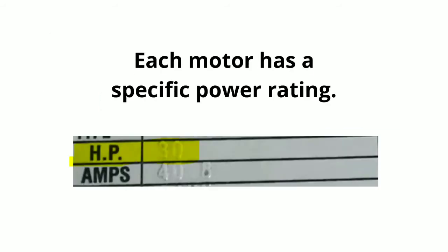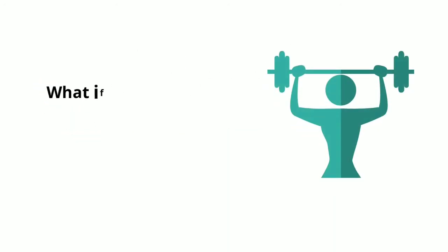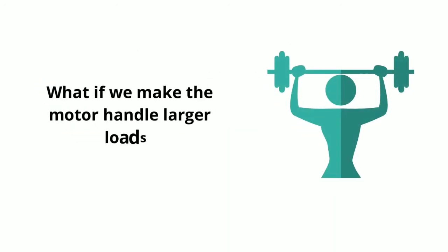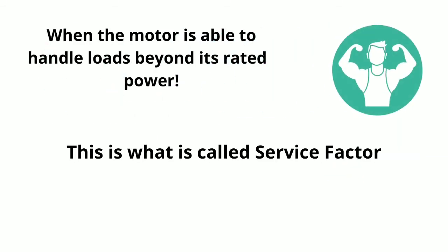Each motor has its power rating. This motor is 30 horsepower. But it can handle a larger load of 34.5 horsepower. This is because its service factor is 1.15, which means that this motor can handle 15% beyond its rated power.